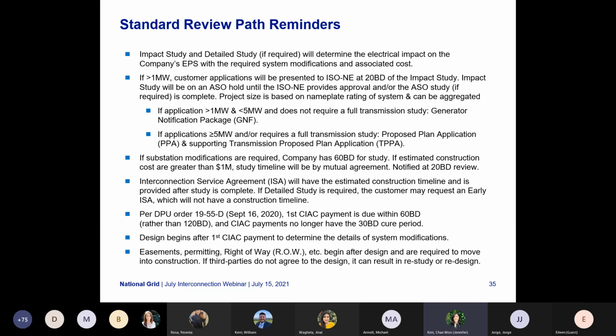If a project is greater than a megawatt but less than 5 megawatts, it does not require a full transmission study, it would be a GNF, versus if an application is greater than 5 megawatts and/or requires a full transmission study, it would need a PPA as well as a supporting TPPA. And then if substation modifications are required, the company has 60 business days for the study, as well as, if estimated construction costs are greater than $1 million, then the study timeline can be adjusted by mutual agreement. You would be notified at the 20 business day review if any of these timeline changes are impacting your project. And then the ISA will have the estimated construction timeline and is provided after the study is complete.